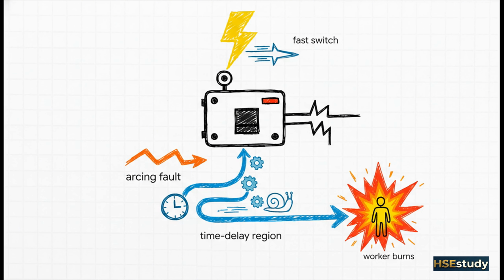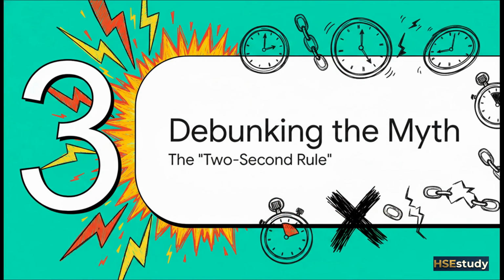The breaker thinks, oh, must be a motor starting, and it just waits. And for those critical seconds, that worker is being cooked. And this dangerously long clearing time leads directly to the single biggest, most dangerous myth in all of arc flash analysis, the infamous 2-second rule.